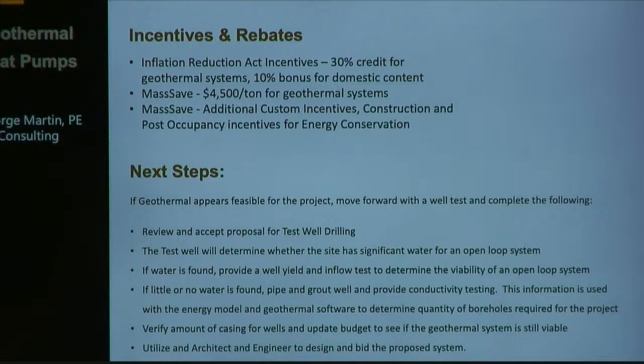But we always do redundant heat exchangers in open loop systems so that if one goes down, you can always operate the system on the other one. We implement some auto back flushing occasionally, depending on what the water quality looks like. So, in general, they're both very low maintenance, but it also matters how you design them.